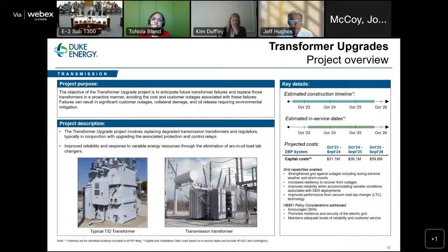When a transformer or a regulator fails catastrophically, there's often release of oil. There is often collateral damage due to the size of this equipment and the amount of energy that's stored in there and the amount of oil that's stored in there. So in addition to just that, asset replacement costs that come in a substation can be very significant from a cost standpoint and also from a time standpoint for recovering from that outage event. So again, these are reasons why we want to proactively address these assets that are at end of life, replace them prior to failure, prior to the customer being impacted, and prior to the grid being impacted by that failure.